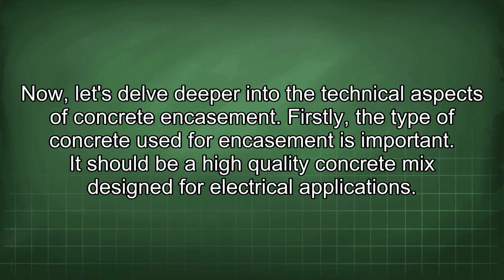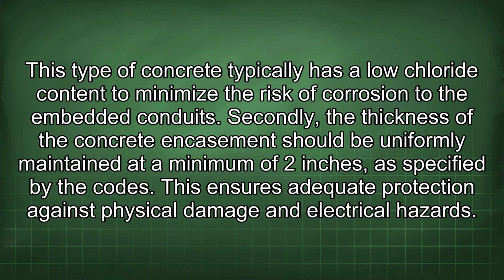Firstly, the type of concrete used for encasement is important. It should be a high-quality concrete mix designed for electrical applications. This type of concrete typically has a low chloride content to minimize the risk of corrosion to the embedded conduits. Secondly, the thickness of the concrete encasement should be uniformly maintained at a minimum of 2 inches, as specified by the codes. This ensures adequate protection against physical damage and electrical hazards.